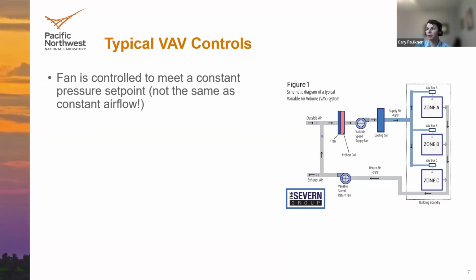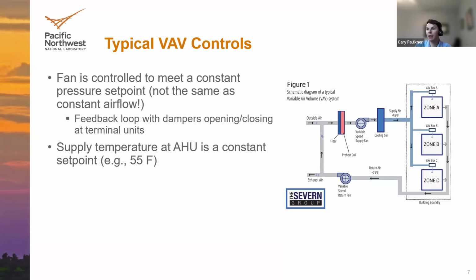Conversely, as the dampers close because the zones don't need as much air, the static pressure will increase above the set point, and then the fan can slow down to maintain that constant pressure set point. So really that pressure is a key part of the fan control and how that airflow is modulated based on the downstream needs of the zones and those damper positions. Whereas at the central air handling unit, the supply temperature might be a constant set point like 55 degrees Fahrenheit or 12 degrees Celsius, which is going to ensure that you have enough cooling. That's going to be cooler air that ensures the zones that need cooling will be sufficiently cooled. And then you have the reheat downstream to provide heating to zones as needed.